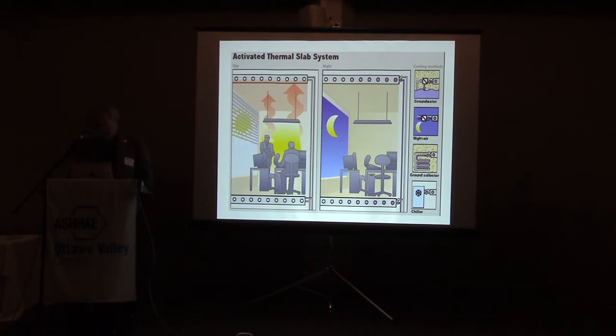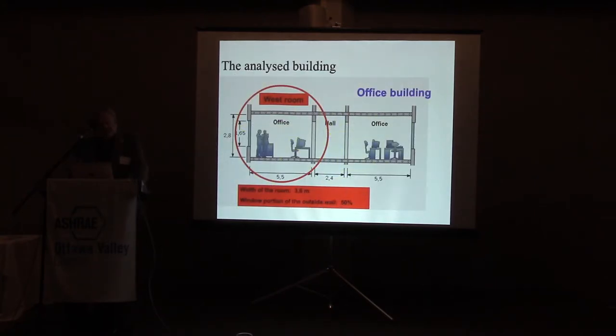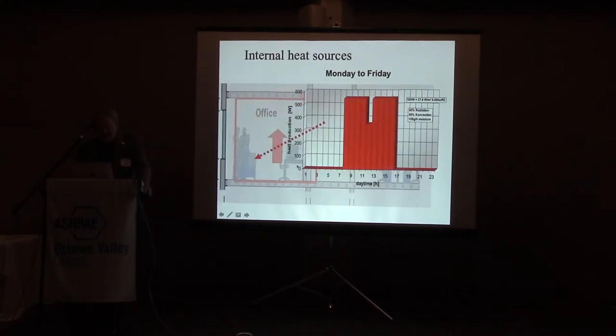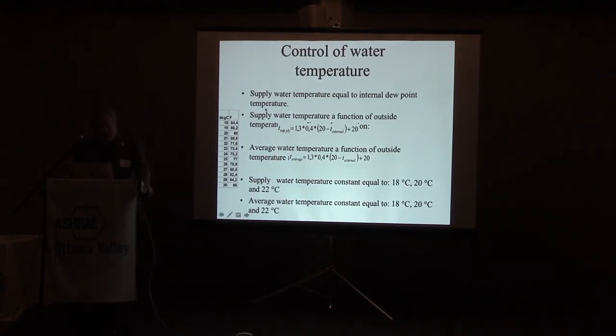So let me show a little how we evaluate, for example, this TABS system where you have integrated the piping in the whole construction. You do a simulation of a building, here an office building. You can have a west, east, south or north room. You define two people maybe, and then you define what windows you have and the internal loads. You put that into your simulation. And then we want to look at how well we can control the temperature in this office. And we look at different ways of controlling.